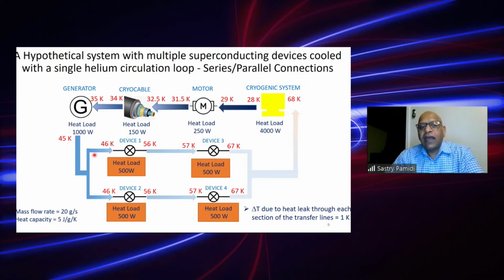And unlike what I showed earlier, it doesn't have to be all in series. It can also be in parallel. The reason we may have to use a parallel connection is that the temperature required for two devices may be the same. Then if we use them in series, the temperature will be slightly higher for the second device. So we can use series for some devices and parallel for others. Because of the large operating temperature range, we can decide how we want to connect multiple devices. As long as we have sufficient cooling power, the same stream of gas can be used in cooling multiple devices.